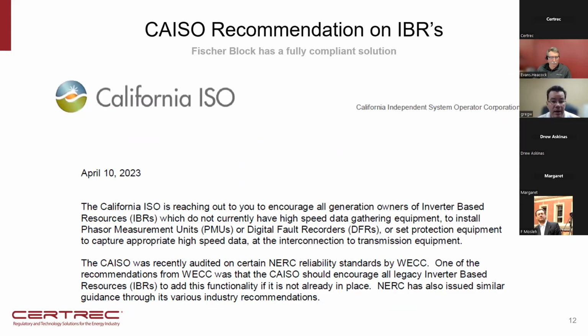So yeah, I think this is the opening paragraph to one of the reports that you were talking about earlier, Evans. Yep. The governing bodies are recommending that high resolution oscillography be installed or capable of capturing devices or signals at these various inverter-based resource plants, whether it's wind or solar or what have you, so that if there is an event out on the grid and the IBR plant goes offline, there's a waveform capture so that diagnostics analysis can be carried out in order to implement corrective actions.